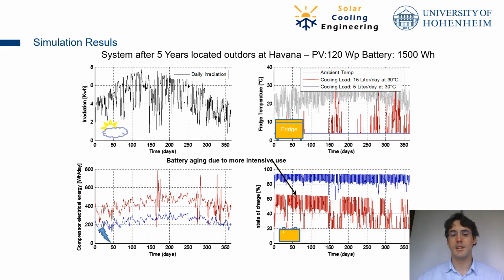And this is not coming from the thermal losses, which remain the same. This is coming from the cooling load. You have 3 times more cooling load, more drinks, warm drinks entering the refrigerator, and then the consumption is much higher.